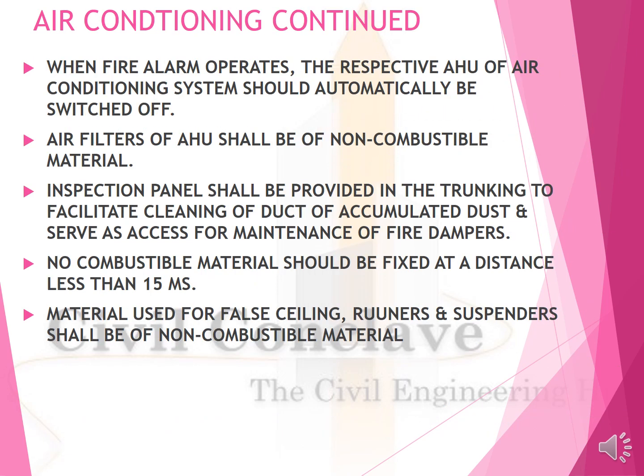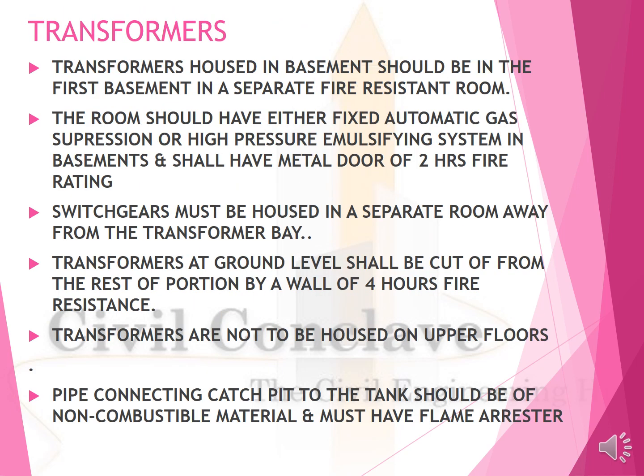When the fire alarm operates, the respective AHU of the air conditioning system should automatically switch off. Air filters of AHU shall be of non-combustible material. An inspection panel shall be provided in the trunking to facilitate cleaning of the duct. No combustible material should be fitted at a distance of less than 15 meters. Material used for false ceiling, runners and suspenders should be of non-combustible material.